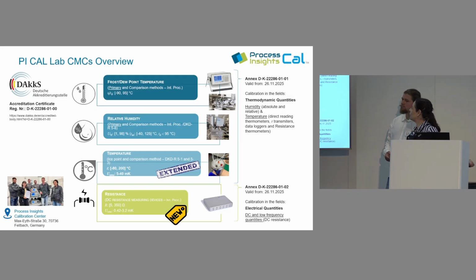So we have accreditation for thermodynamic quantities: frost and dew temperature in the wide range -90 up to 95 degrees, primary and comparison methods; relative humidity from 1 to 98% relative humidity, from -40 up to 125 degrees Celsius, also both primary and comparison. Temperature, we have ice point and comparison methods. We recently extended the range down to -80 up to 200, and also decreased the uncertainty in the liquid bath. We can go from 10 to 17 millikelvin now. And this is very recent.